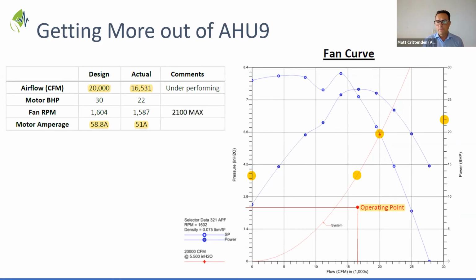Also, maybe the manufacturer submitted the wrong fan curve for this. It would be nice to go in and double check the serial number off that fan. Just very briefly, Matt, do you have a history with this fan? Like, should this have been picked up before?